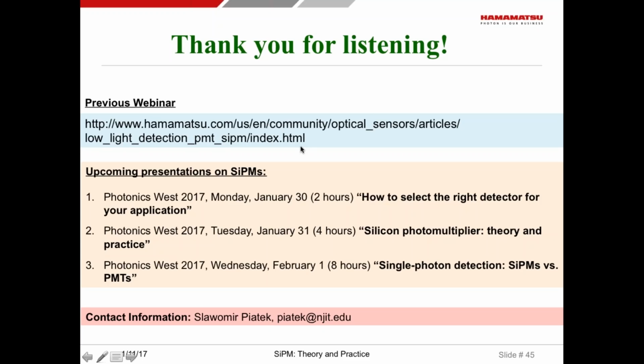Okay, thank you. And our last question here is, can SiPMs replace PMTs in all applications? Not likely. Remembering the very first slide where I justified why SiPM is an exciting device, we saw that the lowest levels that SiPM can detect are not as low as those for PMT. So when we are dealing with photon fluxes of few tenths per square centimeter per second, PMT is still the only photodetector capable of detection. And thus there are some applications like bio or chemoluminescence where we're dealing with diffuse light of very low level. PMTs still hold a great advantage over SiPMs.